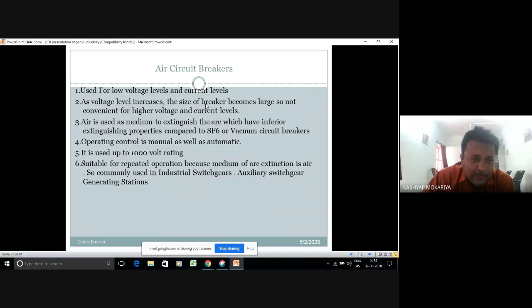So used for low voltage levels. As voltage levels increase, the size of the breaker becomes large, so it is not convenient for high voltage and current levels. Air is used as the medium to extinguish the arc, which has inferior extinguishing properties. Obviously, air has inferior extinguishing properties because we have used natural air. We are not using compressed air or high pressure air, just like the air blast circuit breaker. We do not have superior properties like SF6 or vacuum circuit breakers.